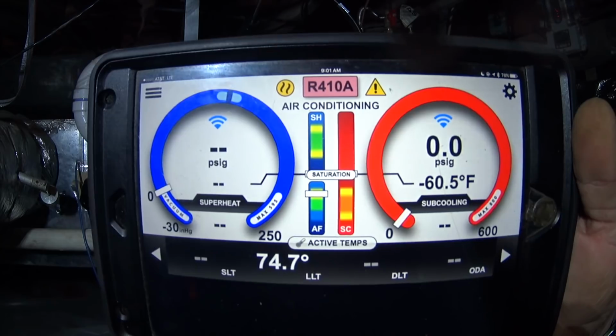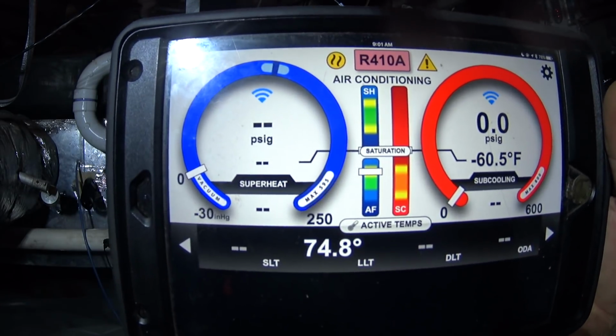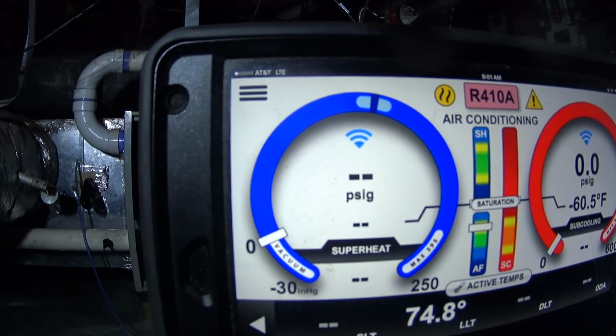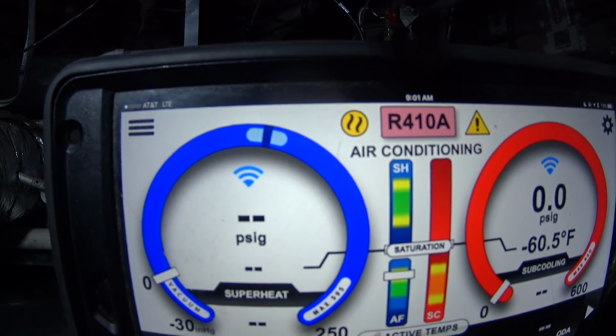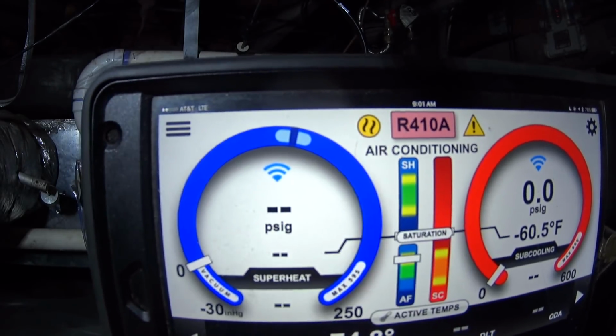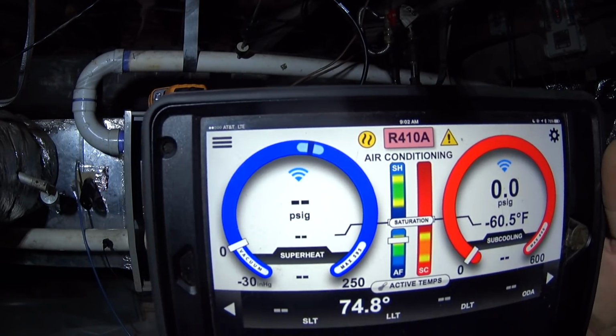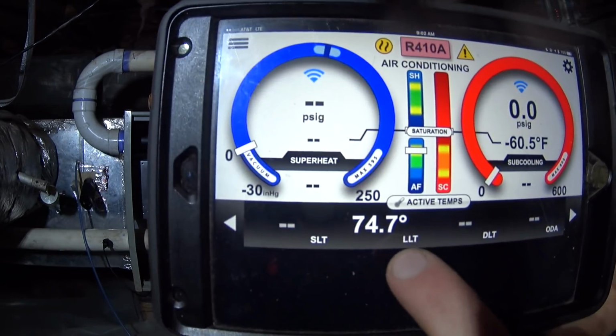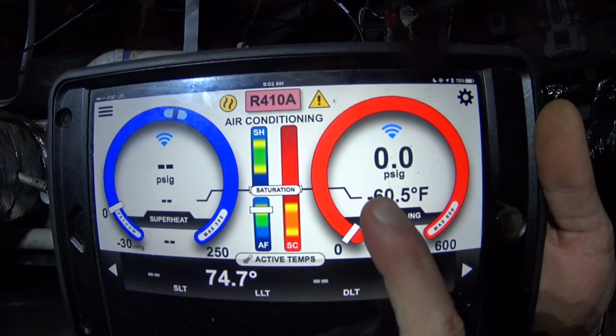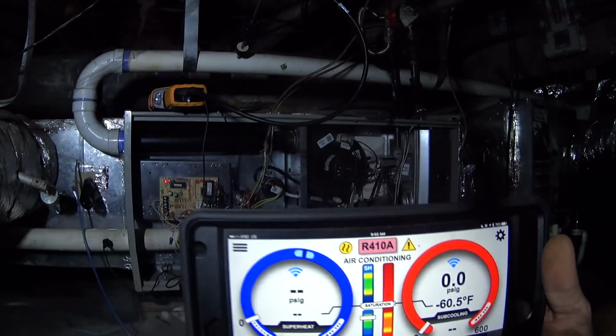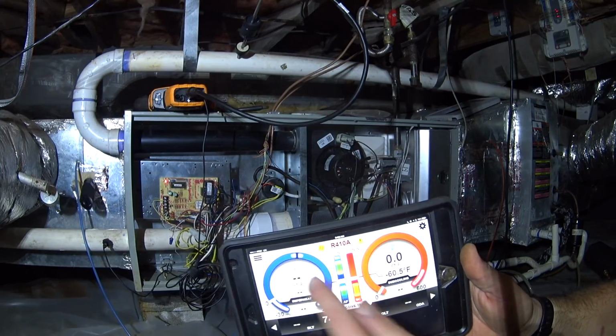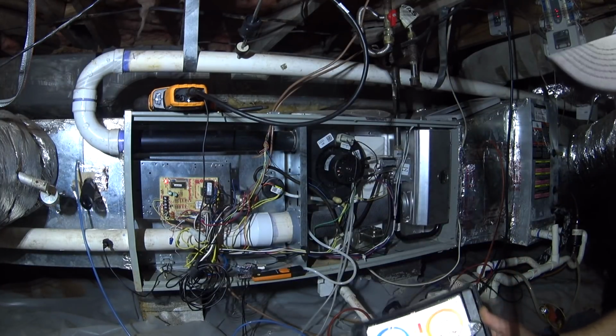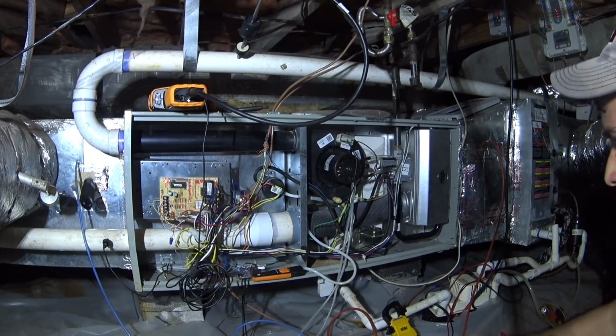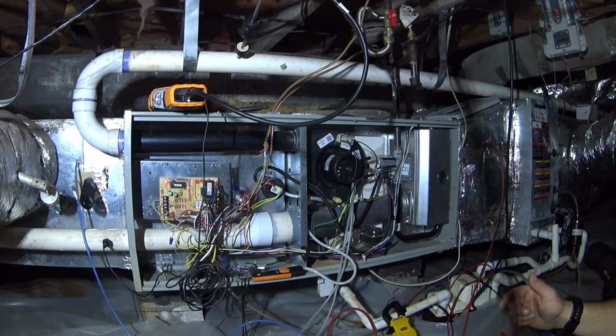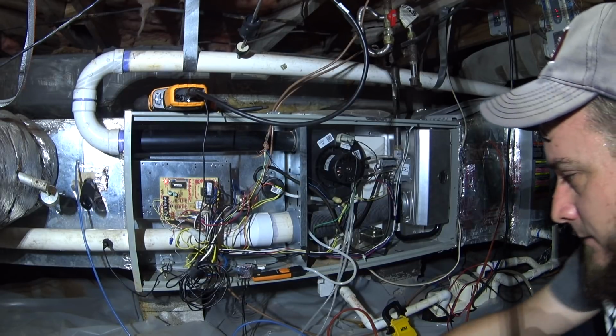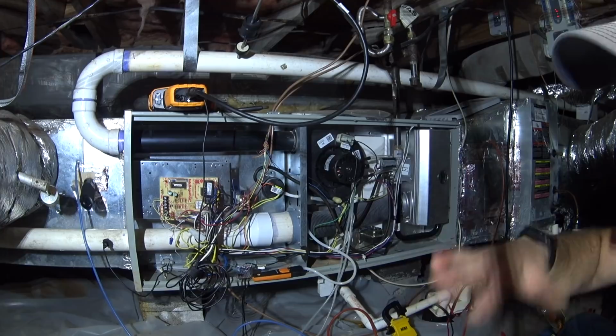One of the stipulations that iManifold software dictates is that you maintain liquid line temperature before you're going to get the balanced system indicator, which is a green check mark right there. So I've got my liquid line temperature and my liquid pressure probe, high pressure probe, connected. Even though it's not necessary, it will give me that check mark and let me know when the airflow is balanced out without having to actually go check the numbers and see if the temperature is balanced.